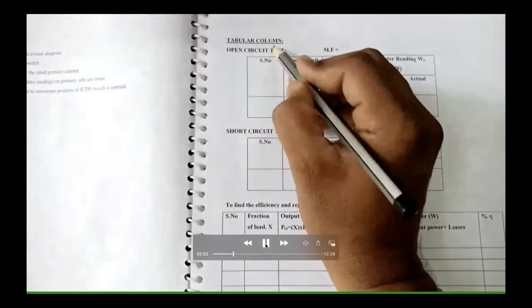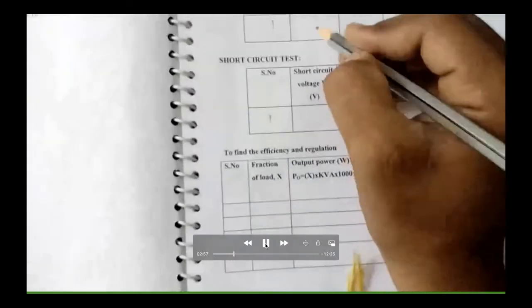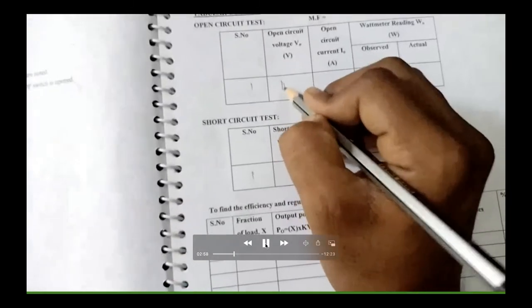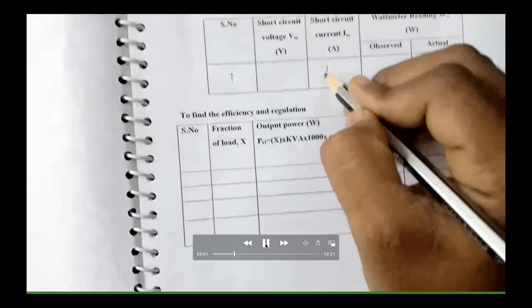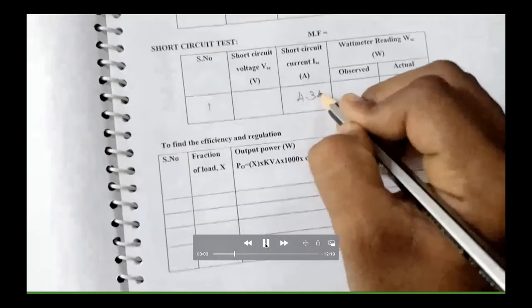Coming to the tabulations, we have only one open circuit voltage and one short circuit current. So we have only one value to be tested. The open circuit voltage will be 115, and the short circuit current will be 4.3. If you keep that, you can find out the rest of the values. So note the multiplication factor for open circuit and short circuit.